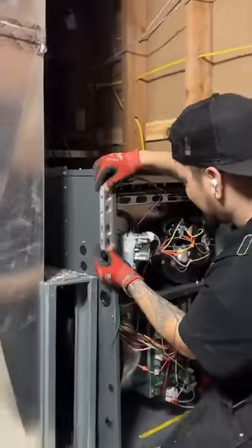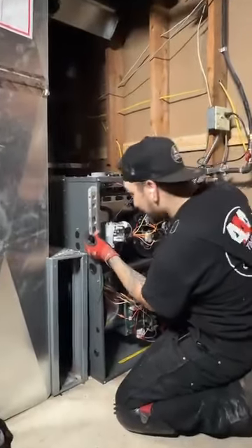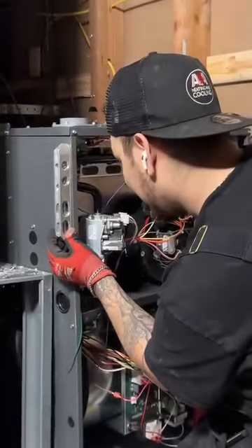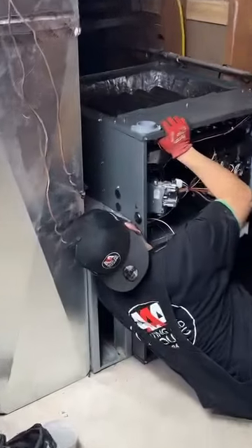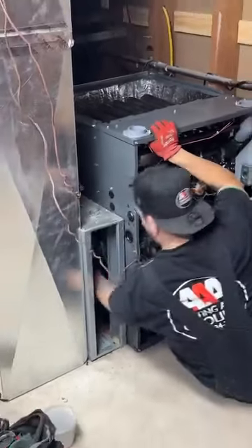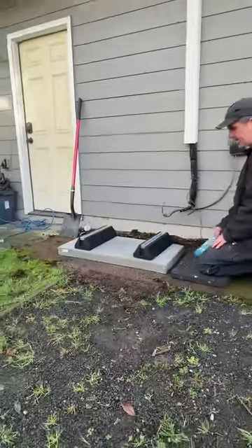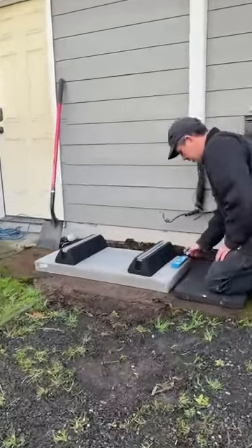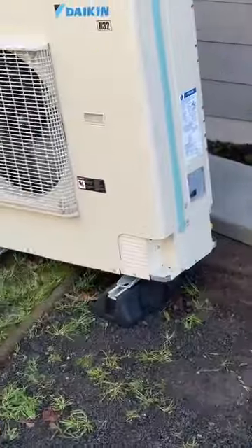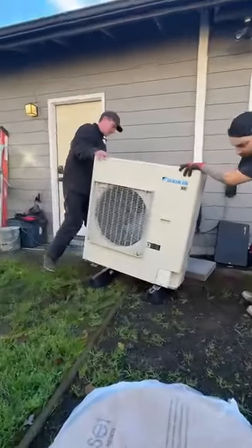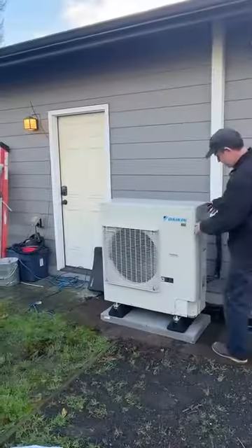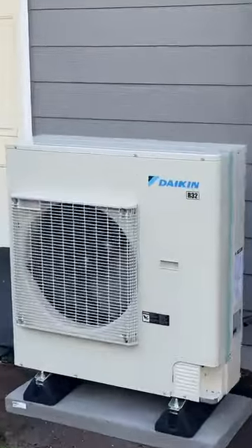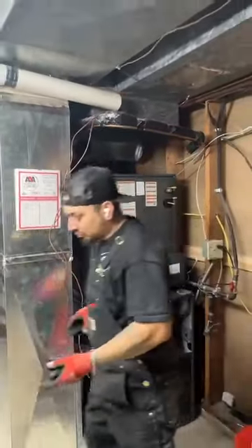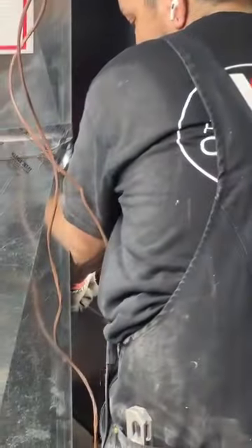With this unit being a 90% furnace, it will produce water, so we have to make sure that this unit is completely level before proceeding forward. From here, we reattach the filter cabinet to the new furnace. Meanwhile, outside, we have leveled the pad and added risers for the new heat pump to sit on. We install the risers to the bottom of the new unit and place it perfectly level onto the newly installed pad for the system. Back inside, we install and secure the indoor coil on top of the new furnace.